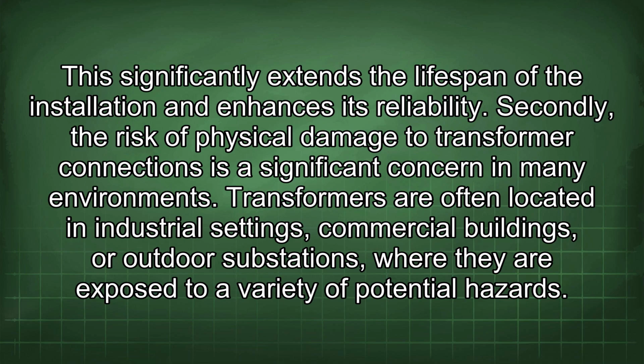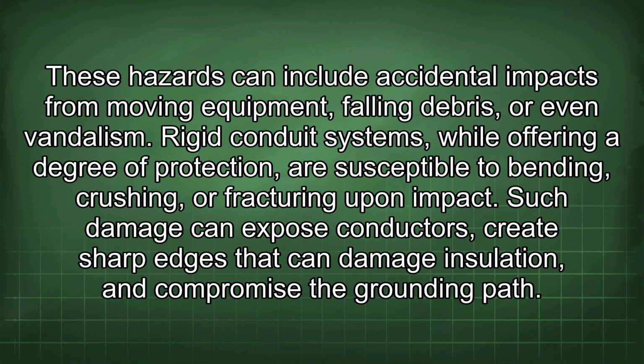Secondly, the risk of physical damage to transformer connections is a significant concern in many environments. Transformers are often located in industrial settings, commercial buildings, or outdoor substations, where they are exposed to a variety of potential hazards. These hazards can include accidental impacts from moving equipment, falling debris, or even vandalism. Rigid conduit systems, while offering a degree of protection, are susceptible to bending, crushing, or fracturing upon impact. Such damage can expose conductors, create sharp edges that can damage insulation, and compromise the grounding path.